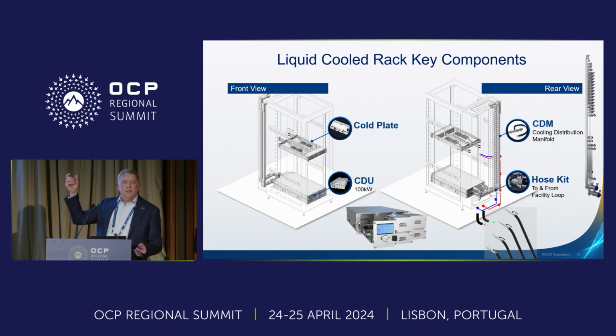We have a system built and designed to bolt right to the back side of the rack, with red and blue connectors. It's simple: you either have hot water or cold water connectors, used to connect in just like a power distribution unit on the back of a rack. Finally, you need a hose kit to hook this up to the facility's water loop, which will typically have a particular type of connector you need to use.